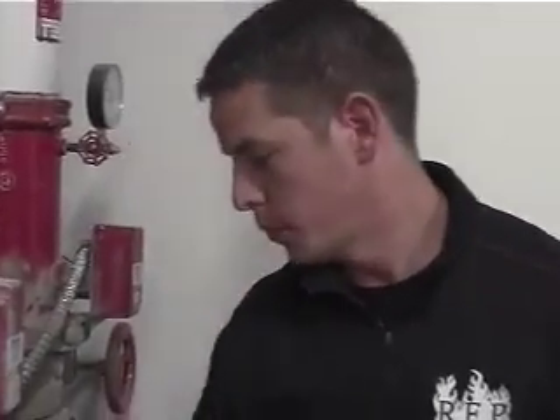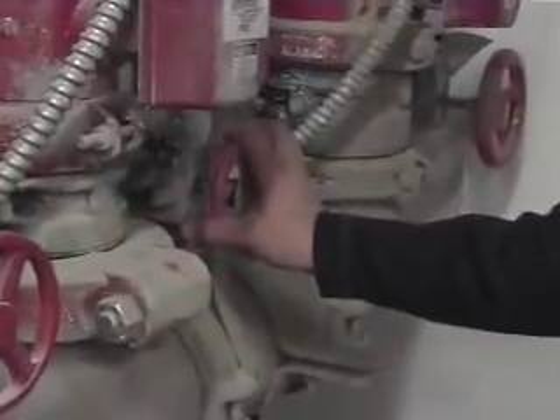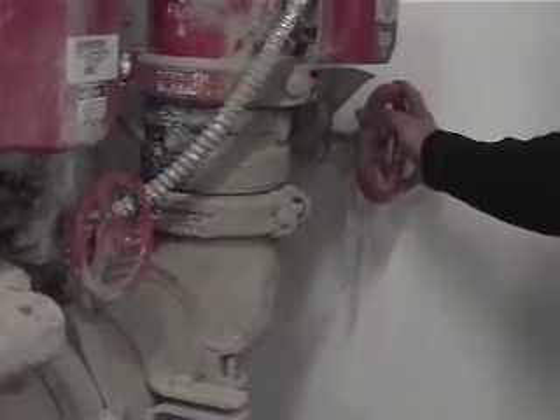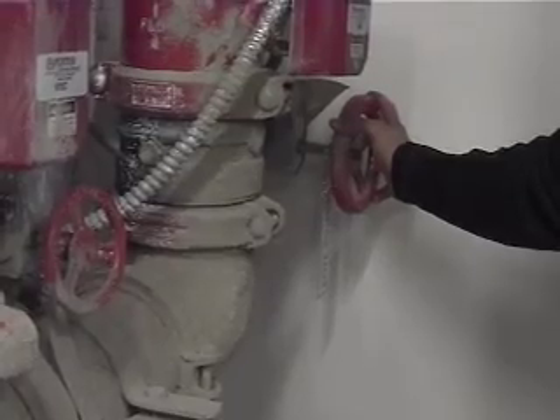Got an auxiliary drain right here for your low point drain. With the drain being on the first floor going outside, the basement zone will be trapped. So after you drain the pressure off, you want to use that to drain the basement water off. You've got a shut-off valve right here for the basement, and a shut-off valve right here for the standpipe supply.